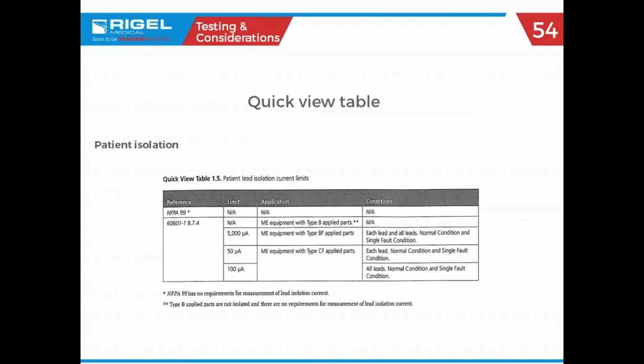I really tried to avoid a sales pitch. All the equipment that I happen to have up here is mine. In this one and its next brother down, we have the ability to specify what that isolation voltage is: 500 volts, 250, 100 or 50. Other safety analyzers like this one are more focused on NFPA 99, hence 99 as part of the name. It's really focused on NFPA 99 test standards, where we don't have to do that. So if you have to do it, and it sounds like you do, you just need to be sure that you have the appropriate safety analyzer that allows you to do it.